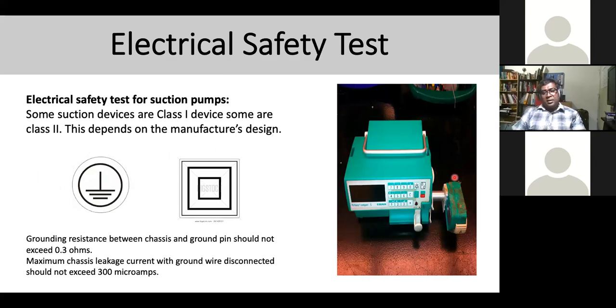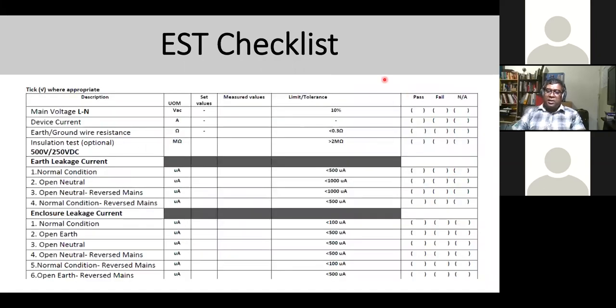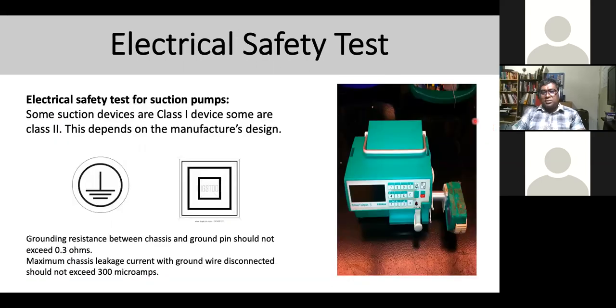For electrical safety, most of this particular device can be class 1 or class 2, depending on the manufacturer's design. So when you talk about class 1, the grounding should be below 0.3. And chassis leakage current should be less than 300 microamps. So all these are very important details that you need to do. When you look at the back of the device, you can see this particular symbol, either the class 1 symbol or the class 2 symbol.